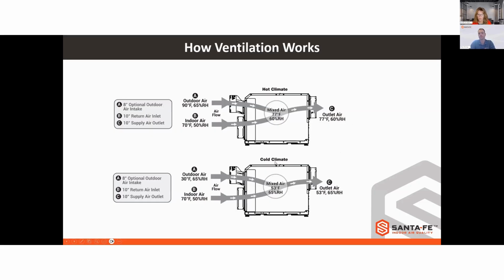And again, we've got a colder climate illustration to indicate again, we're not just bringing in that cold outdoor air and distributing it through the house. We are tempering it with the air inside. And we got the 8-inch here, but these other two are 10-inch ducts. The return and supply to the dehumidifier are 10-inch ducts.